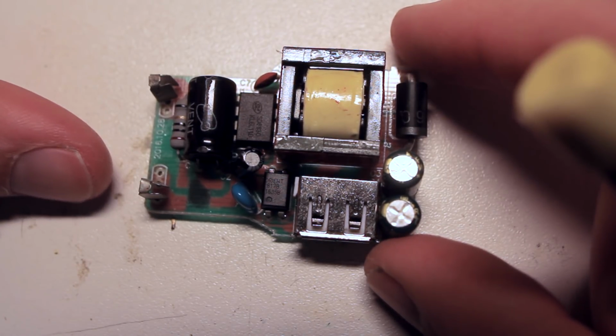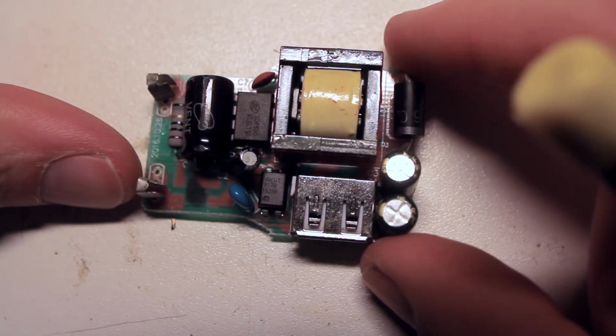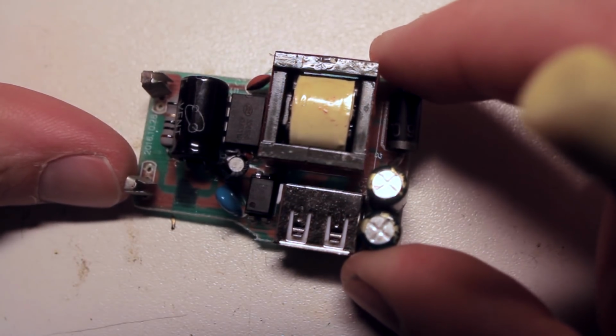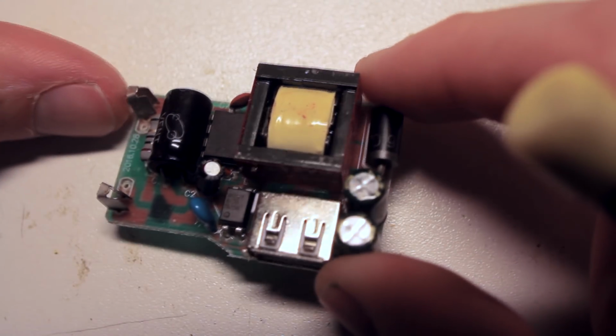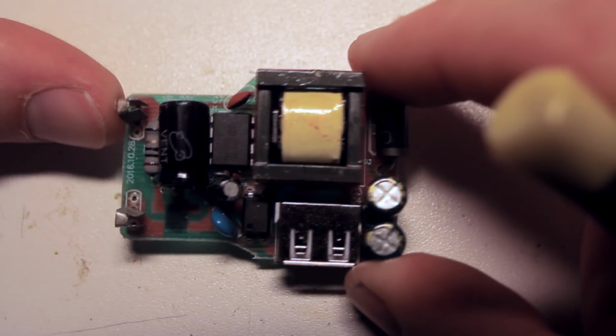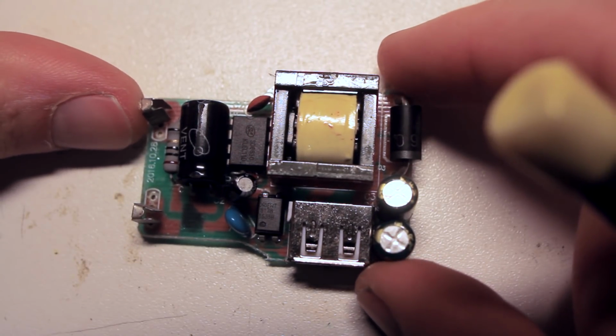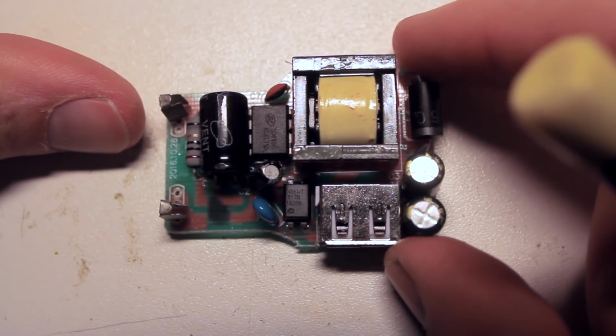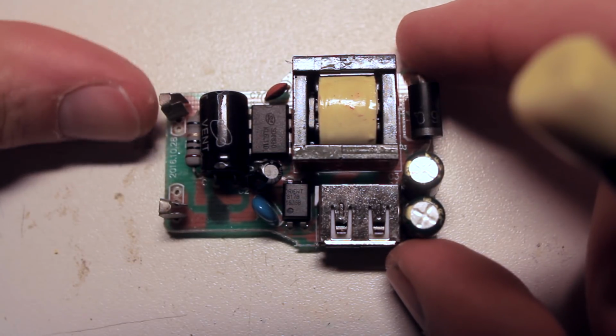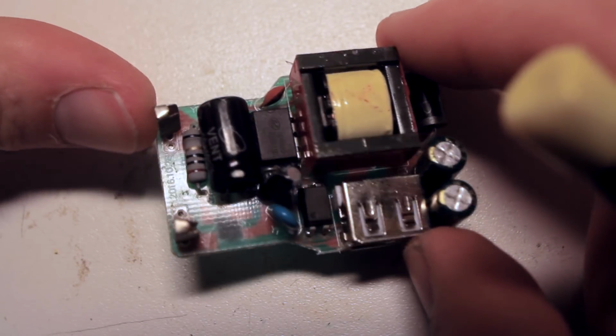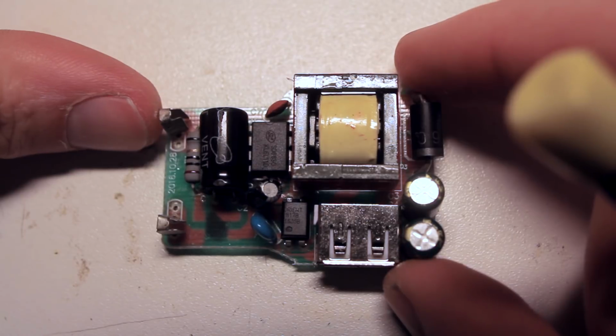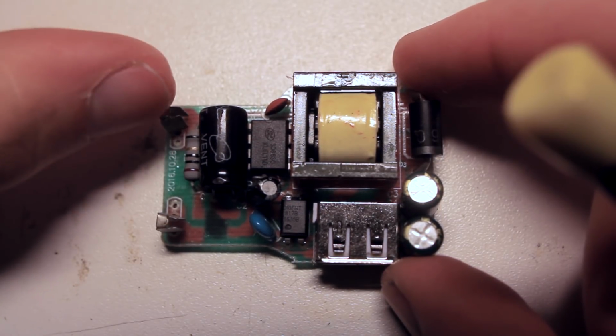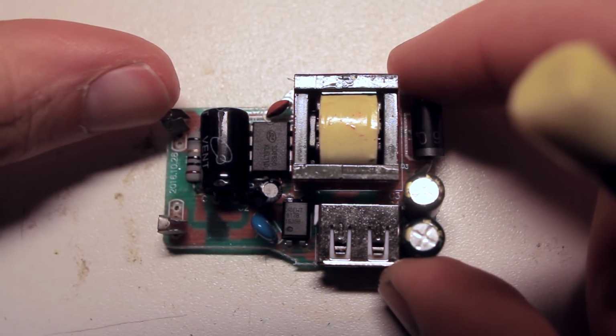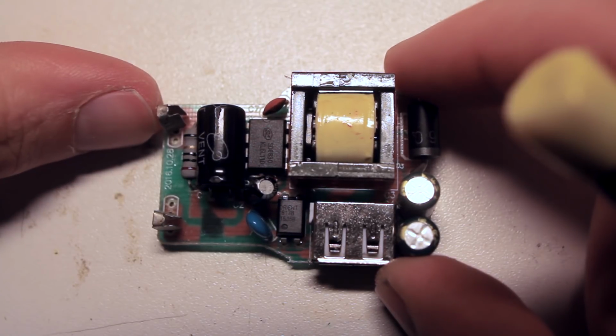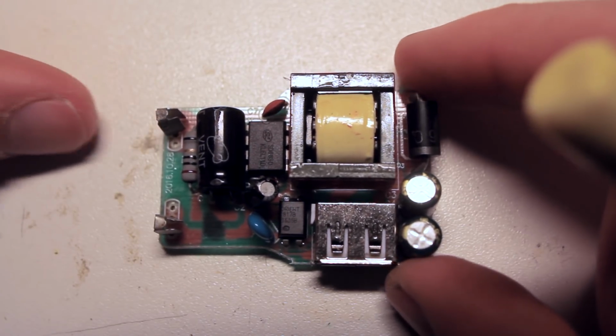You will get dissimilar metals rubbing against each other and essentially rusting on each other. And this will eventually lead to bad contact. That is actually a fire hazard, but I don't think it's categorized as a severe fire hazard. So this is kind of okay, but not really. I would much rather see proper crimping contacts, there are just better ways of contacting this.